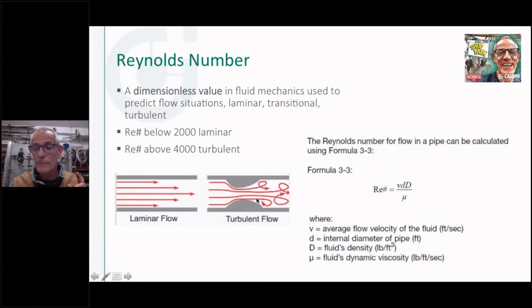Now there is one condition where we might not want to go to turbulent flow conditions. Think about this: if you take a district system, for example, we've got a central boiler plant, and maybe the pipe is going underground to all these different buildings. Well, we don't want to lose a lot of heat through that underground insulated piping. So an engineer might design that so it's working under laminar flow, a real slow flow condition, probably under a foot per second velocity, depending on the pipe size, so that he gets most of the heat from the boiler room out to the buildings before it gets lost to the ground. So there are conditions where an engineer might look at laminar flow and decide his pipe sizing and his pumping flow rates to stay under that condition. But once it gets to the building, once it gets to the heat emitters, we need to have this turbulent condition so we can exchange that heat out of the fluid stream as best we can.